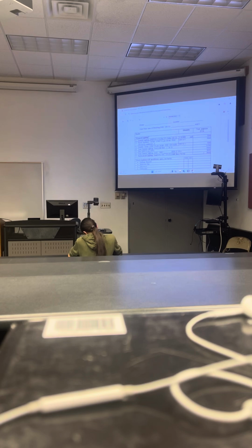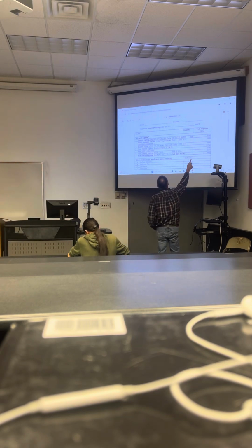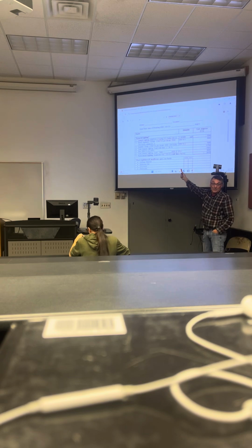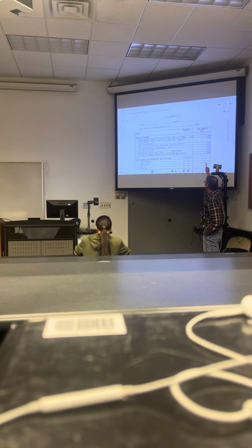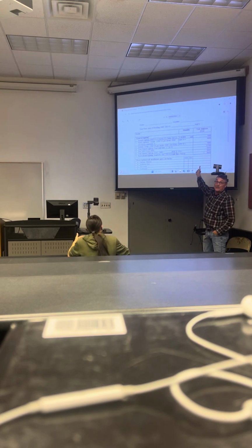How did you get to the 6,045? Yeah, there's 50 in the first one, 25 down there in the second, number 7, net general lighting load. Right, so it's the square feet, 7,200. Then we add in 2 small appliance circuits of 1,500 each. Then you add in the laundry circuit, which is 1,500. Comes out to a total of 11,700.